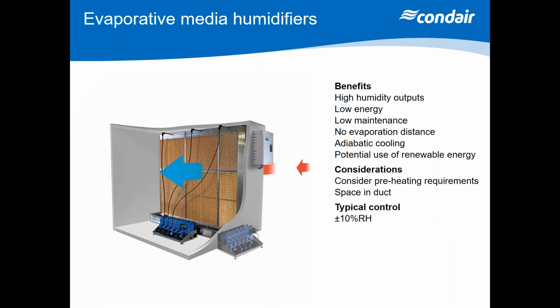So next, we're going to turn to adiabatic systems. We've looked at steam. When we look at adiabatic systems, there are a number of choices, as there are with steam systems. But our first port of call would be an evaporative media humidifier. Here you can see one. It's built to match the internal dimensions of the air handling unit, and it's pretty simple.